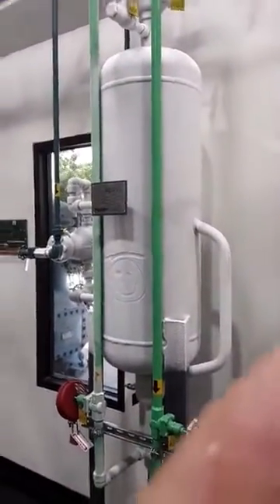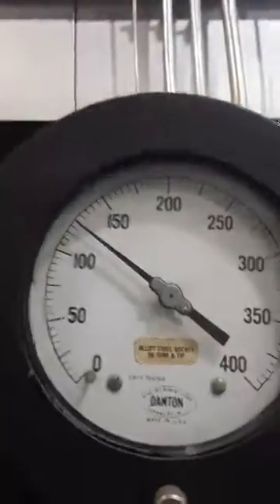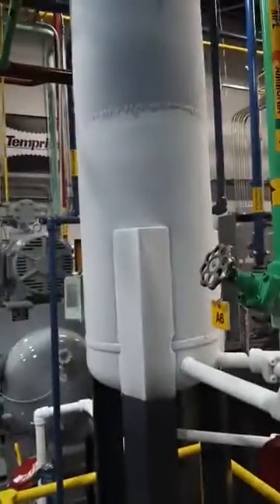I've been playing with this for three hours — don't know if I want to go back to work. The anhydrator is working. We're going about 8 PSIG on our suction and discharge 135, with the anhydrator going.